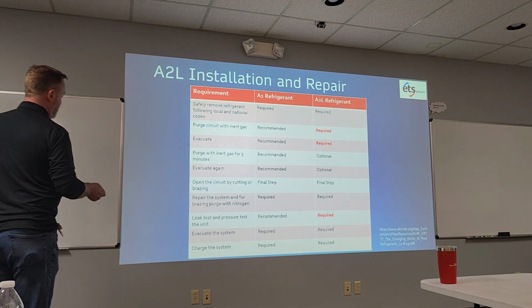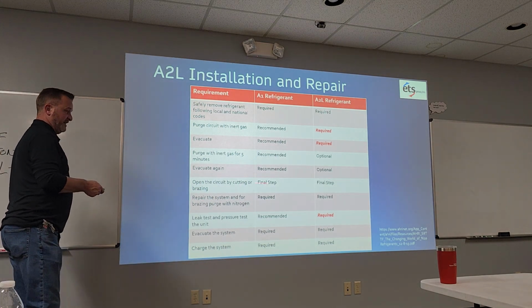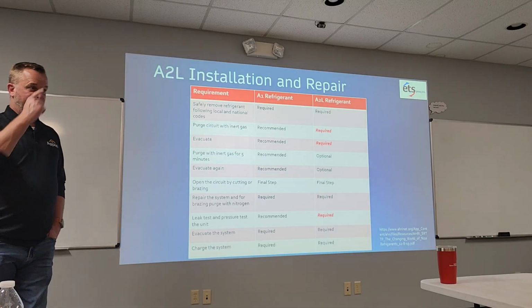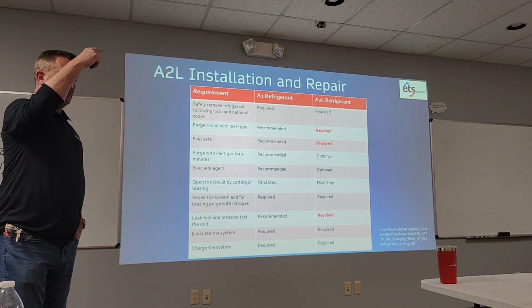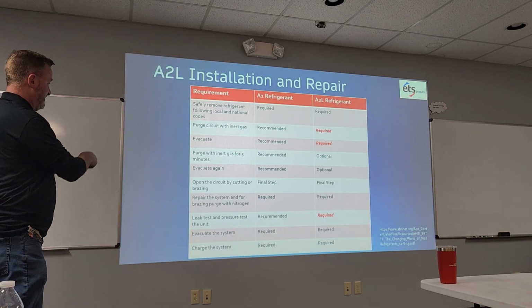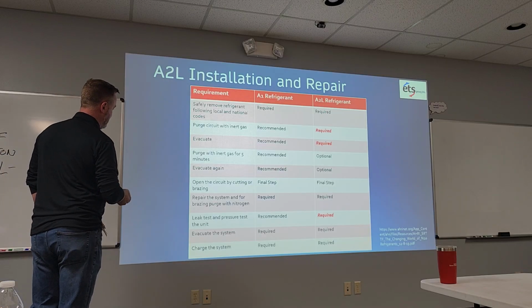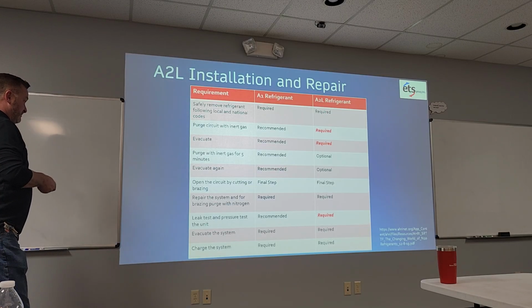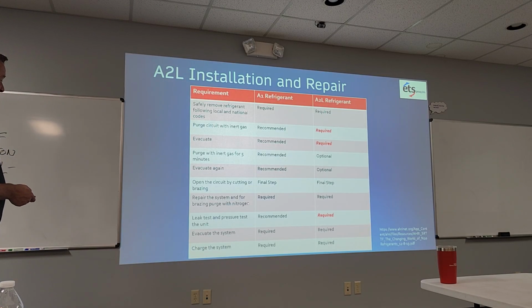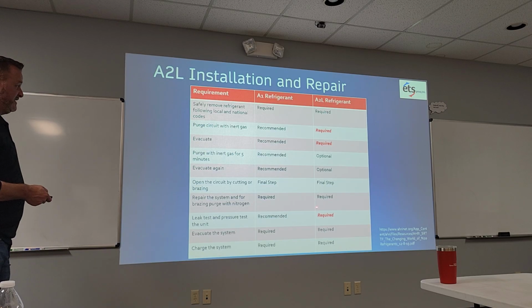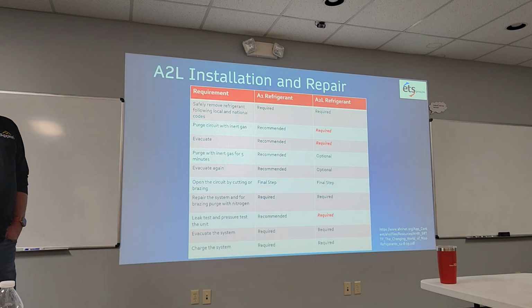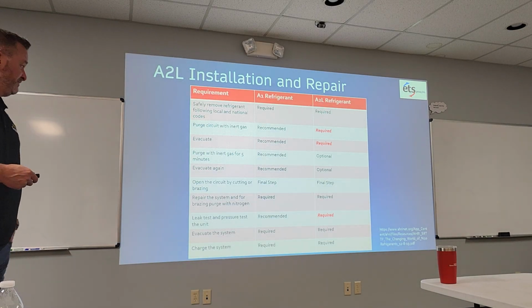Then from there, we're allowed to open the circuit by cutting or brazing. No problems - we've recovered, we've purged, we've evacuated, now we get down to opening up by brazing. Then we do our changes, our repairs, and repair the system, brazing, purge with nitrogen. I always recommend that one way or the other. You have to purge with nitrogen when you're brazing.